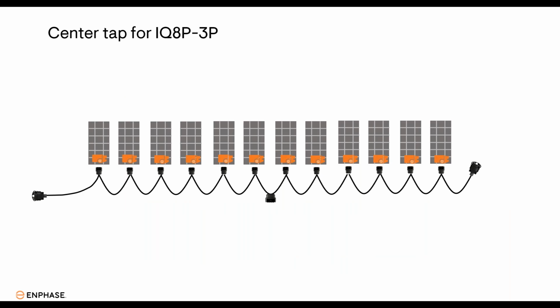Placement of the center tap plug does matter. After every 6th connector, there is a center tap plug on the QD cable. Here's an example of a simple circuit with 12 microinverters, starting with the very first connector in the QD cable box. That means right in the middle of that circuit, you'll have a center tap connector between the 6th and 7th microinverter. That's where you plug in your center tap adapter and run your home run back over to the sub panel board.